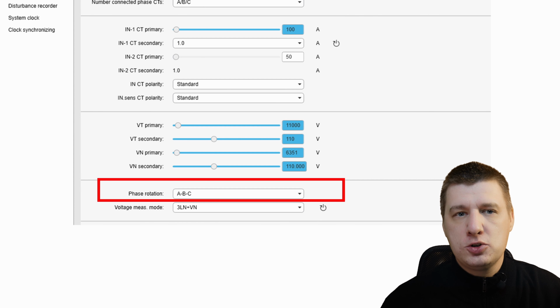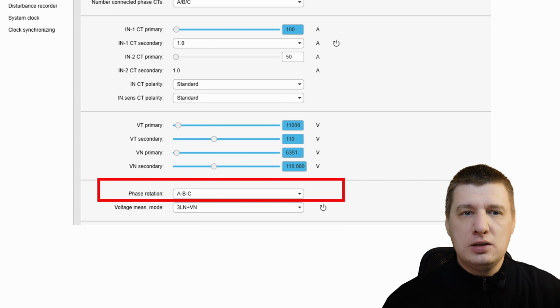Why does it matter? Certain functions like negative sequence overcurrent and directional phase overcurrent are mathematically dependent on the phase sequence. The source states it is mandatory to ensure the correct phase sequence. An incorrect setting here could cause the relay to trip when the system is healthy, or fail to trip during a real circuit fault.